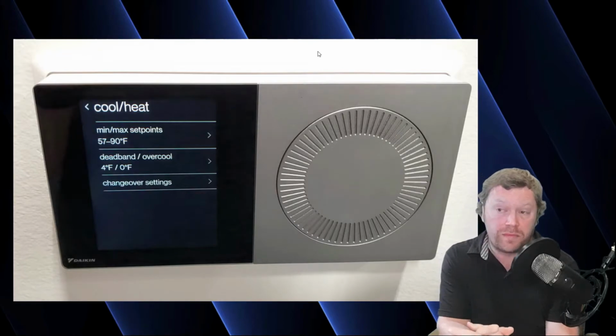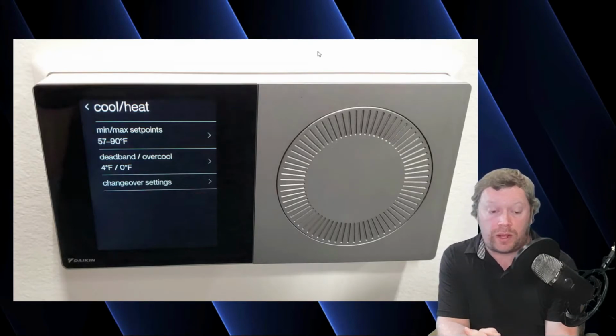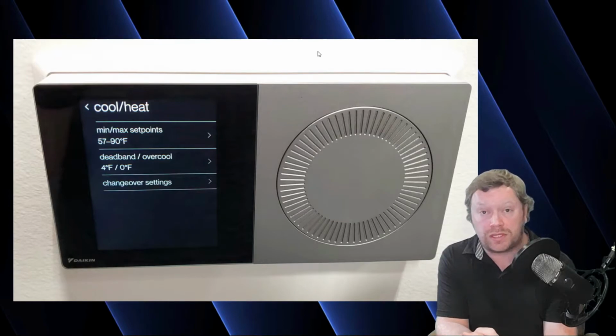And then you're going to have your min-max set points. This is, how high can your thermostat go and how low can your thermostat go. If you don't change it, then technically you can lower your set point all the way to 57 and all the way up to 90 if you really want. For residential applications, we typically don't change this because it's your house. You can do what you want. In commercial applications, we do typically restrict this based on what the building owner wants the tenants to be able to do.